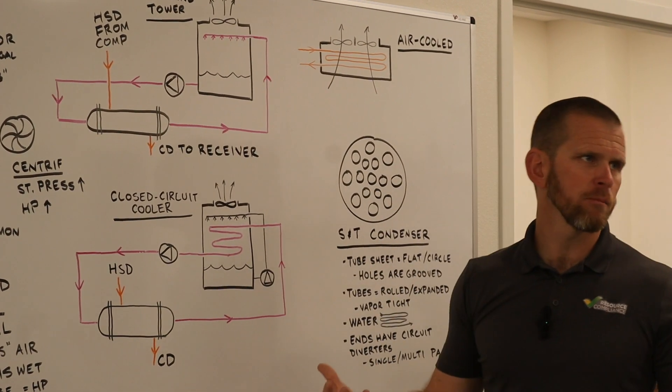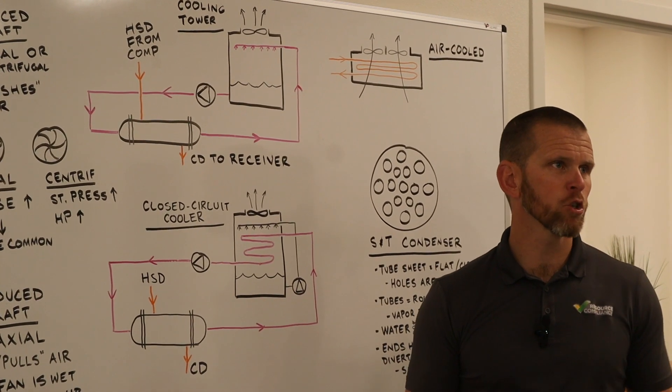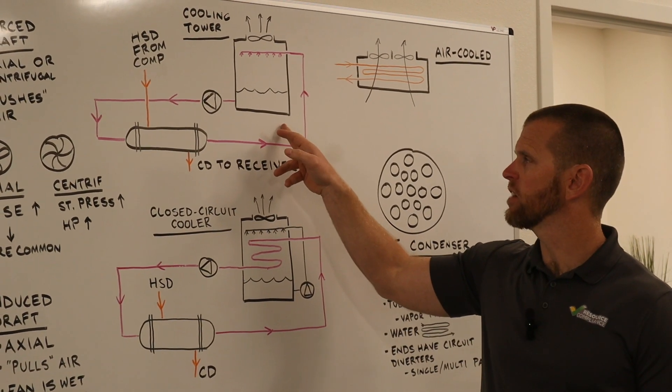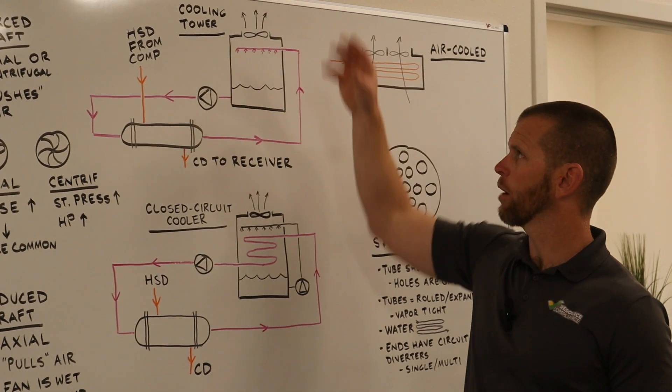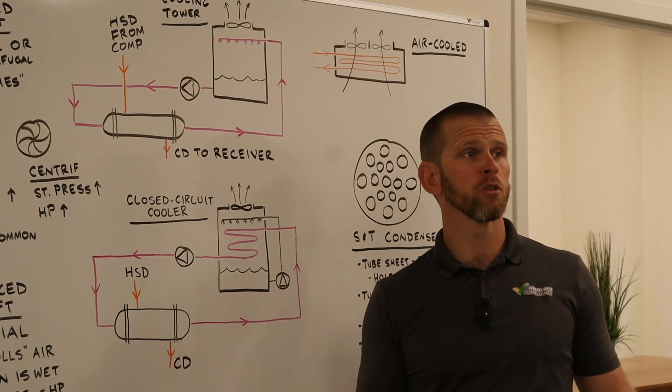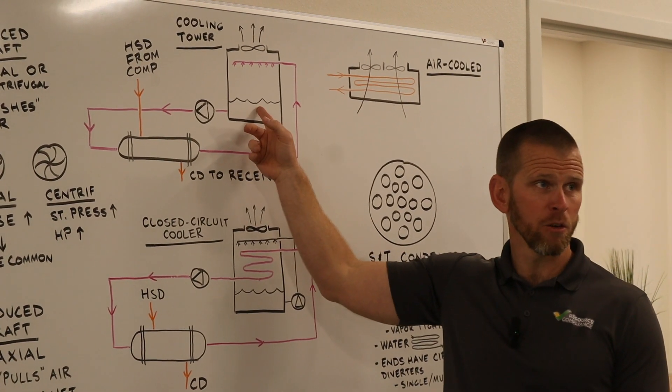Now you might think, well, that seems simpler because you only got one loop. And I guess that's kind of true, but really this is not as good of a system because this fan, which is drawing air through that, tends to bring in a lot of dirt, dust, debris.